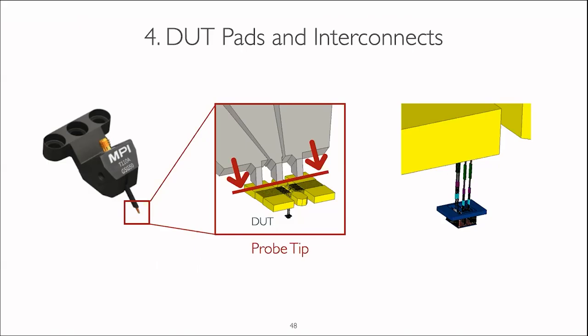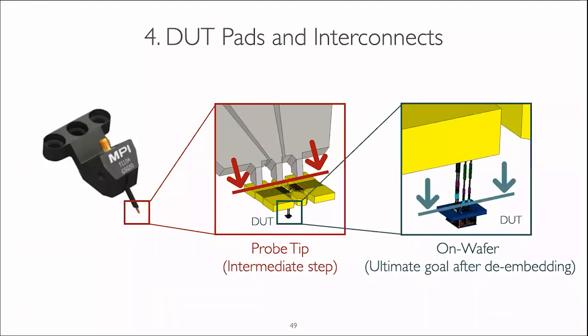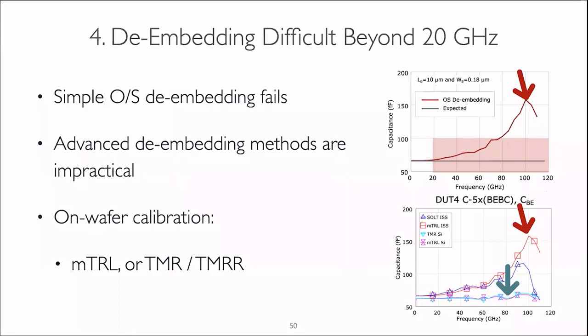The probe tip calibration is not the only step that we need to exercise. We need to do some extra steps like pad de-embedding routines, and shift the reference plane from the probe tip down to the device under test terminals, and get rid of the impact of the device contact pads, as well as the via stack and other device under test infrastructure. These de-embedding algorithms become very difficult to execute at frequencies beyond 20 gigahertz. Industry conventionally uses open and short de-embedding, which captures the device under test infrastructure environment pretty accurately, but only up to 20 gigahertz. If we need to verify extracted model parameters at frequencies beyond 20 gigahertz, it becomes very challenging. We need to use advanced de-embedding methods which require multiple steps; 5 or 7 de-embedding steps are available today, but they are really impractical.